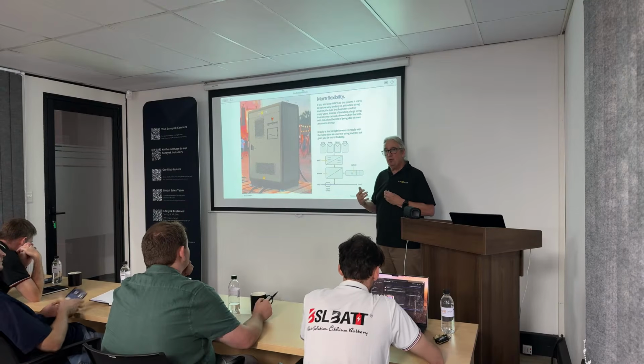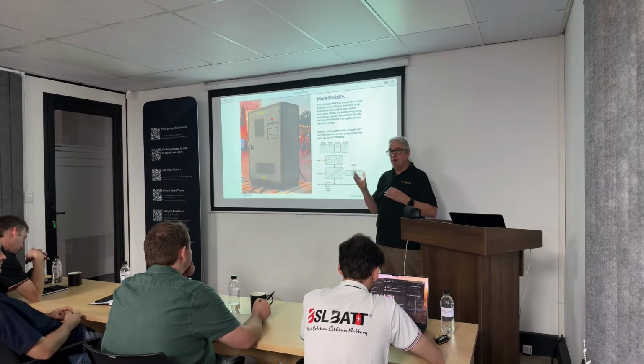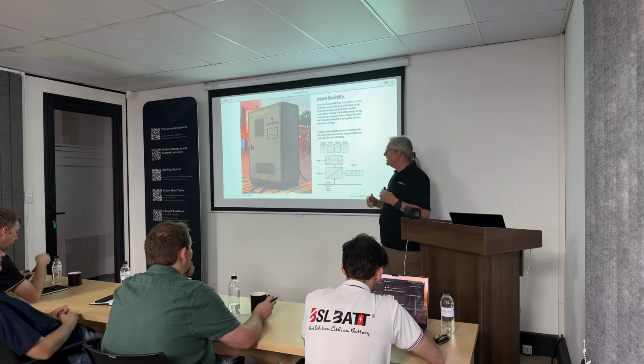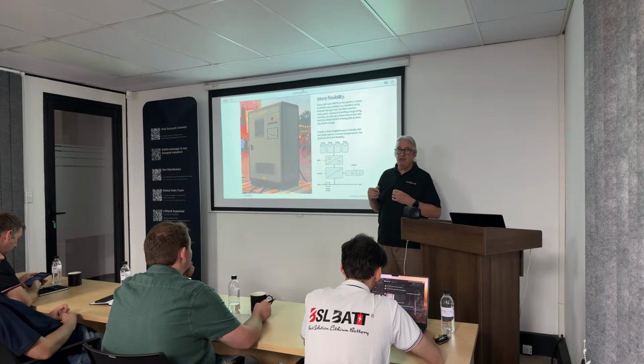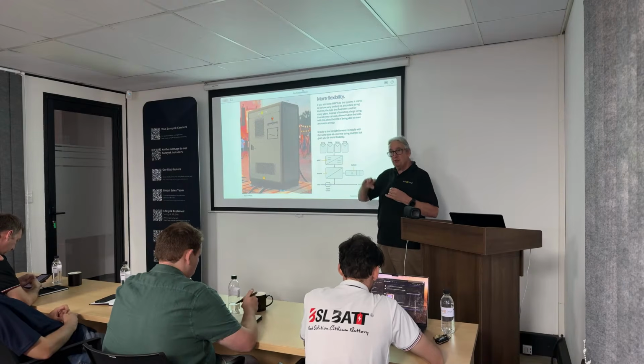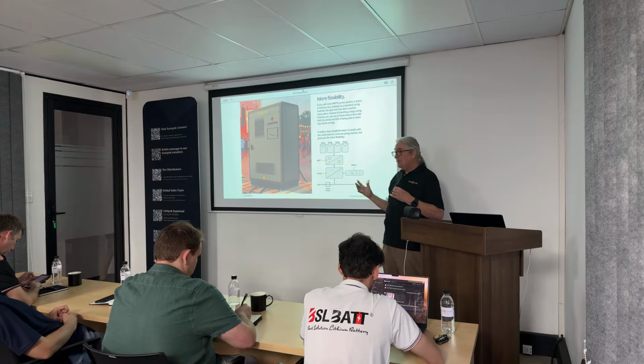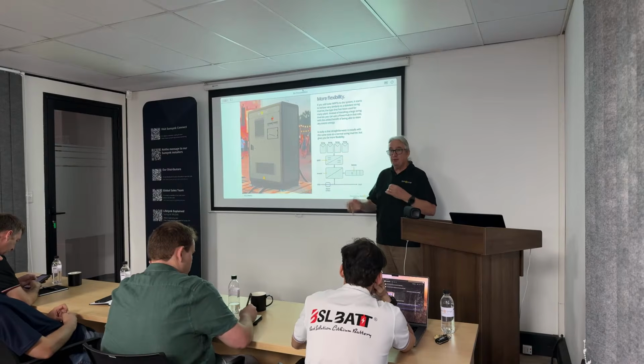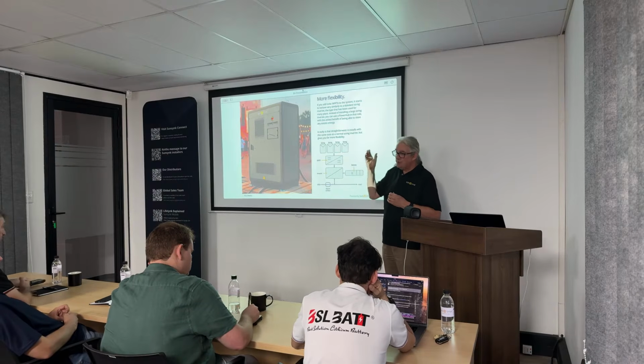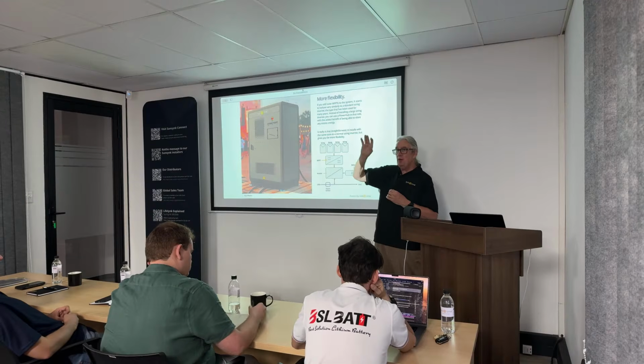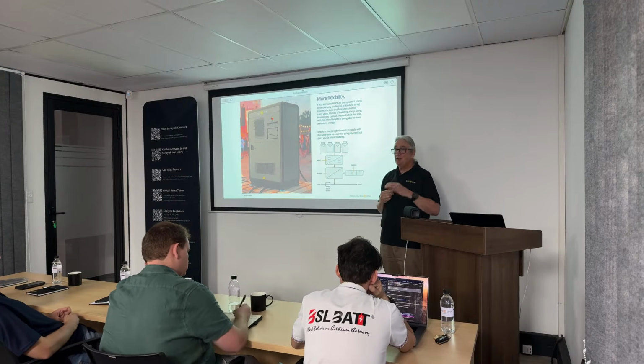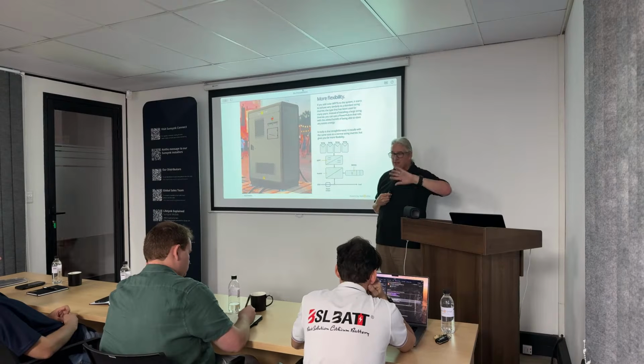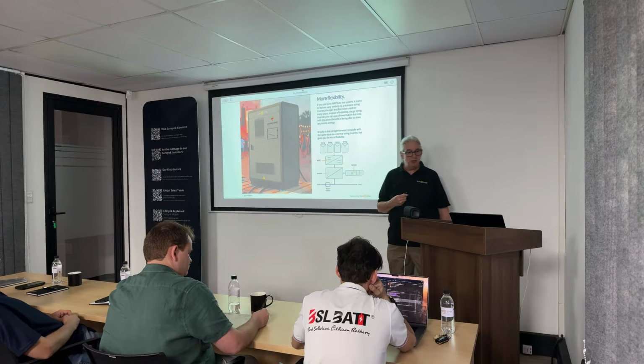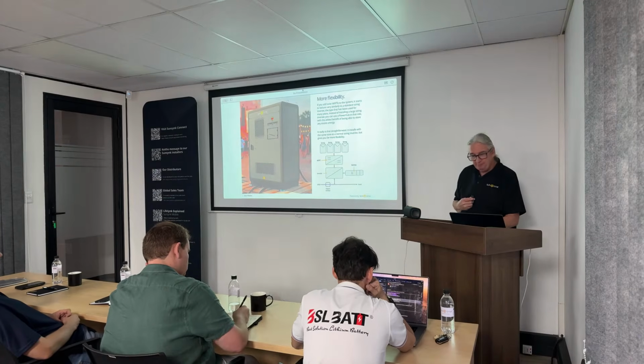The STS operates very quickly, but you're not having the old-fashioned relay swapping things across. It doesn't exist. The only time you have a changeover is if the inverter is in a charge mode and you want to discharge, because the inverters are reversible. Exactly the same as a normal hybrid inverter, the PCS is reversible, it goes one way or the other. So, of course, if the inverter is in a charging mode, it has to reverse. So you then will have a very, very fast, it's milliseconds, changeover. If it is in discharge mode, there's no changeover. So it depends on where it is.